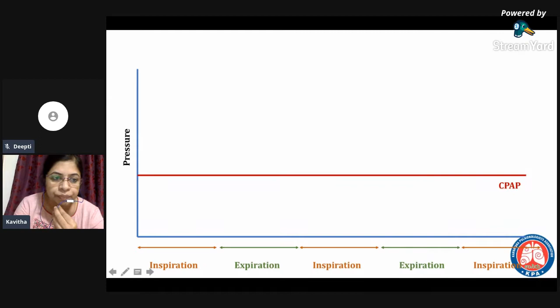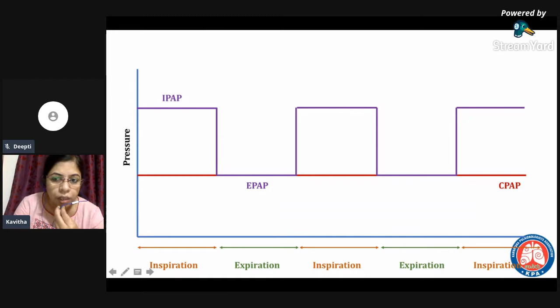However, a BiPAP will have two different pressures, that is an inspiratory pressure and an expiratory pressure. Expiratory pressure is similar to your CPAP, and inspiratory pressure is higher than the expiratory pressure. You decide what is the difference between the two based on your titration and the patient's requirements, the patient's carbon dioxide levels, and minute ventilation, whatever targets you want to achieve. So IPAP, and during expiration, there is a dip in the pressure, that is the EPAP. So this is your BiPAP. So we know what is CPAP and what is BiPAP now.